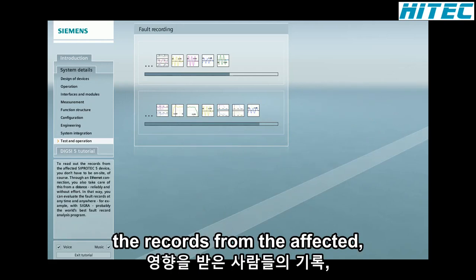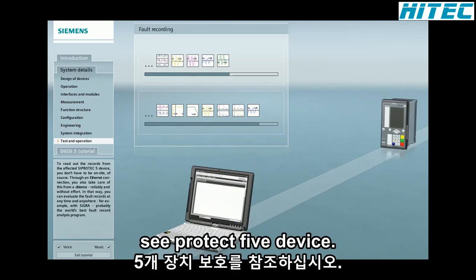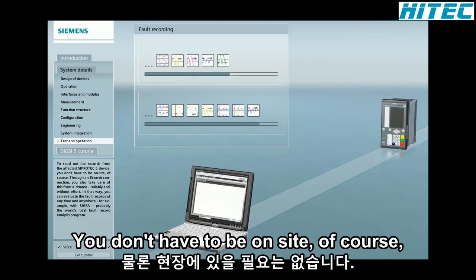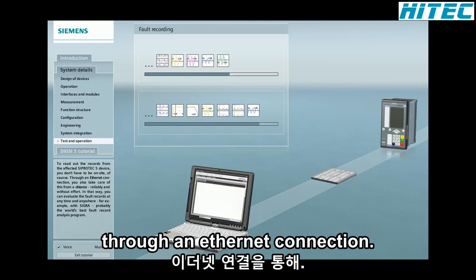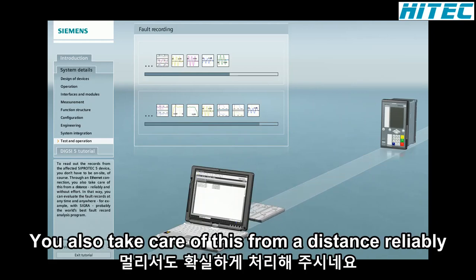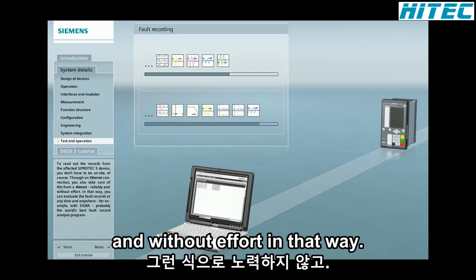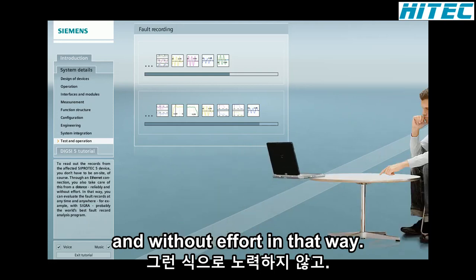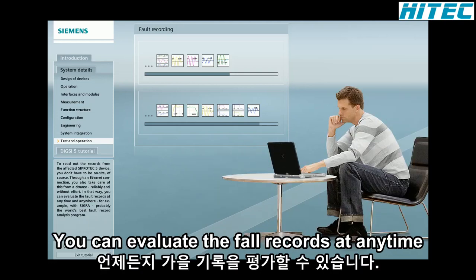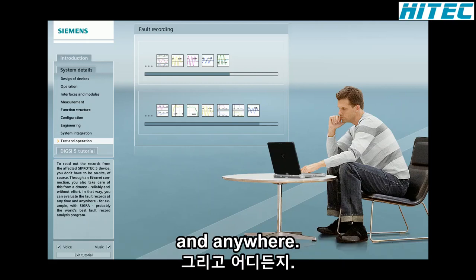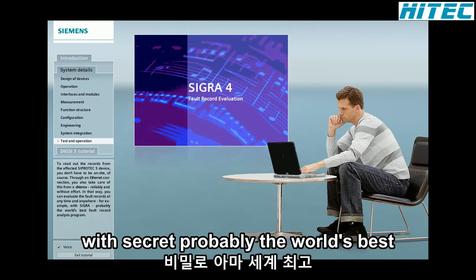To read out the records from the affected SIPROTEC 5 device, you don't have to be on site, of course. Through an Ethernet connection, you also take care of this from a distance, reliably and without effort. In that way, you can evaluate the fault records at any time and anywhere, for example with SIGRA, probably the world's best fault record analysis program.